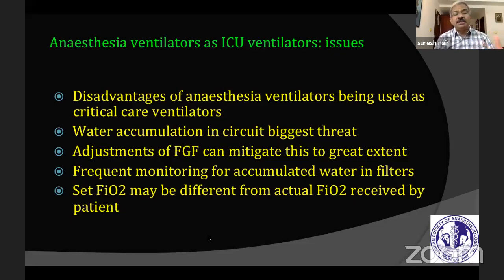But it also causes too much heating of the circuit, as a result of which water accumulates. Water accumulation can be reduced to a great extent by increasing the fresh gas flow, at least to match the minute ventilation of the patient. Now this adds to a problem in different ways.